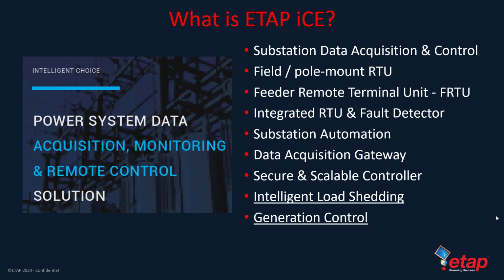It can also be used as a front-end processor because the device can help to communicate to local devices that are either distributed on a substation or across multiple substations. And it offers the security to the user that the data will not be compromised using different solutions such as isolating networks, cybersecurity, and so on. This device also has the capability of enhancing or expanding the ETAP applications, such as intelligent load shedding. It can act as a controller for the solution, or it can act as a device for generation control, where it can communicate directly to the main ETAP server.